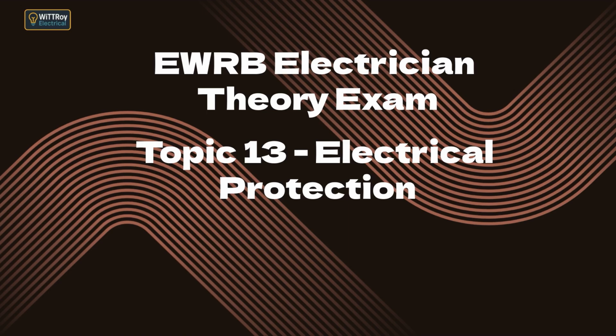13.1e: describe the construction, operation and applications of semi-enclosed rewirable fuses, HRC fuses, miniature circuit breakers, cartridge fuses, fusible links, magnetic overload relays, and thermal overload relays. A semi-enclosed rewirable fuse uses fuse wire that melts under overcurrent, simple but coarse protection. HRC fuses are sealed with a calibrated element and sand filler, giving fast and safe interruption at very high fault currents. MCBs use thermal and magnetic mechanisms to trip on overloads and short circuits and can be reset.